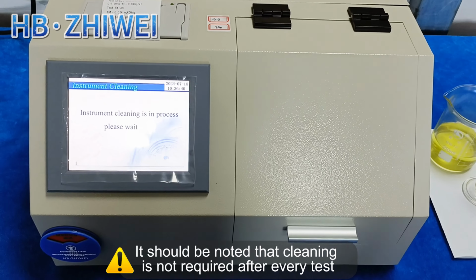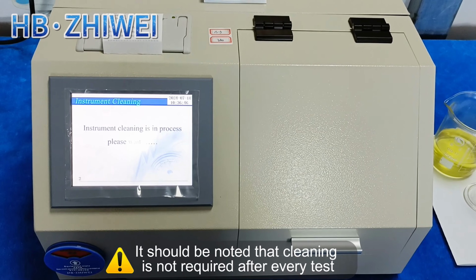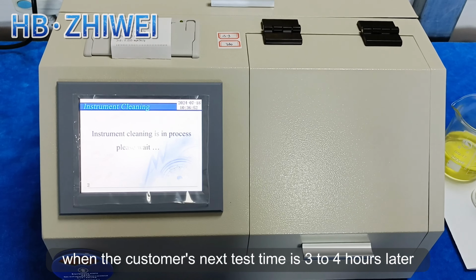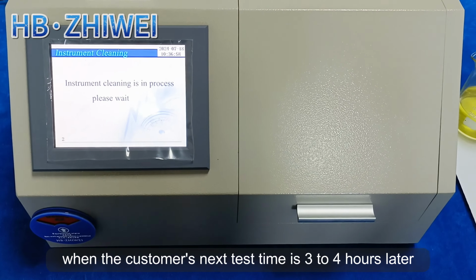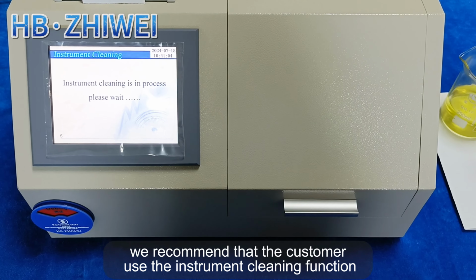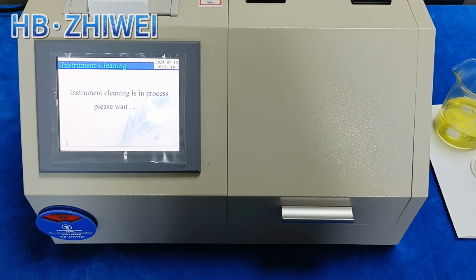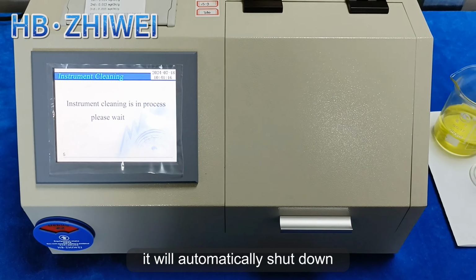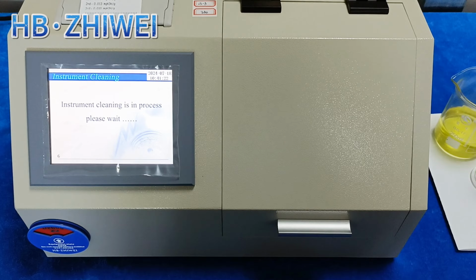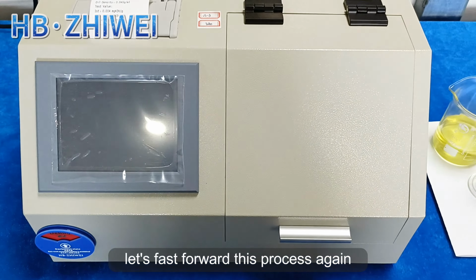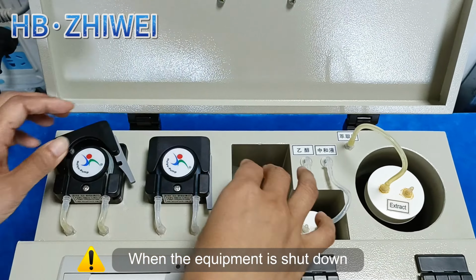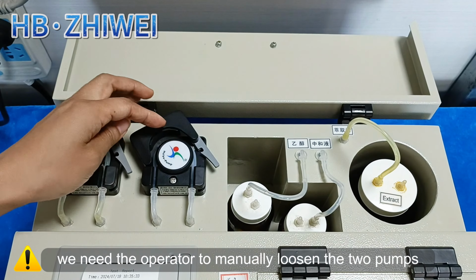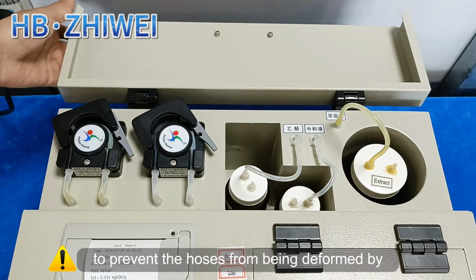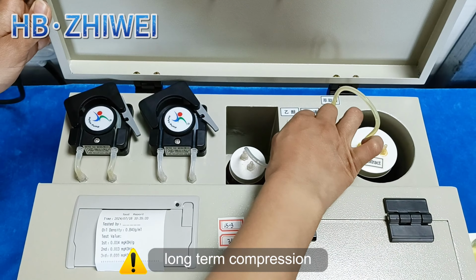It should be noted that cleaning is not required after every test. When the customer's next test time is 3 to 4 hours later, we recommend that the customer use the instrument cleaning function. When the equipment is cleaned, it will automatically shut down. Let's fast forward this process again. When the equipment is shut down, we need the operator to manually loosen the 2 pumps to prevent the hoses from being deformed by long-term compression.